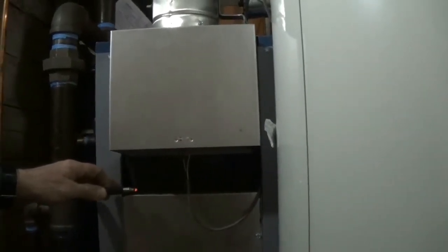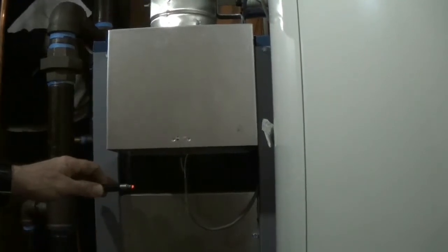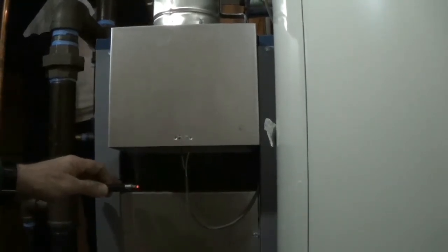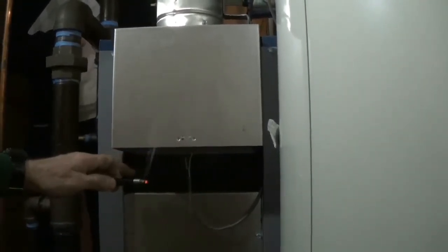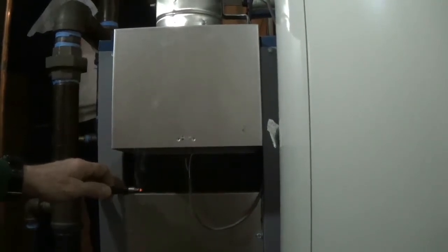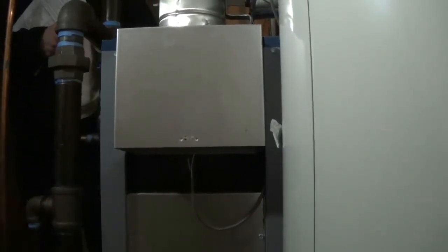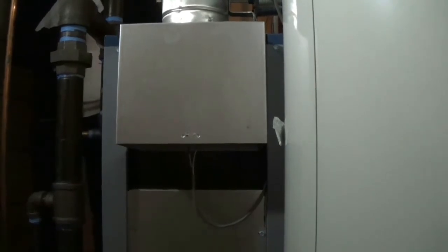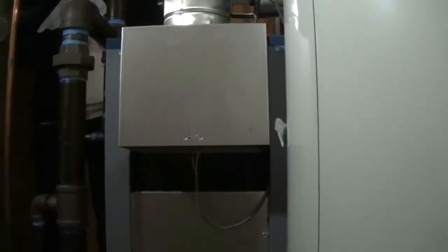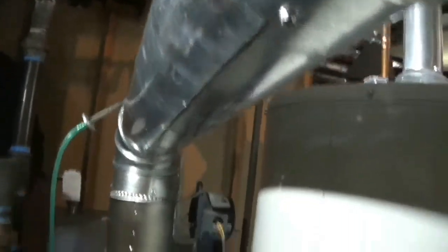But other equipment might take almost all 60 of those seconds to turn the corner and start to pull away the way it should. This is not. And it's been 60 seconds, so this is failed spillage as well under worst case conditions. So quickly we'll measure the draft for this boiler. Now sometimes you get passing draft, but you get failed spillage. It's still a fail, right?